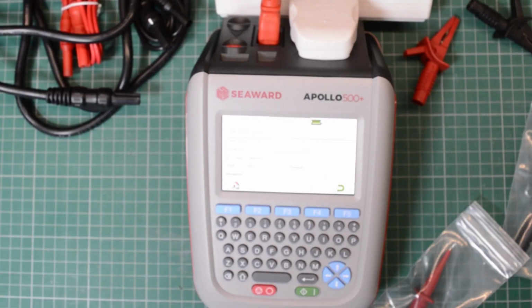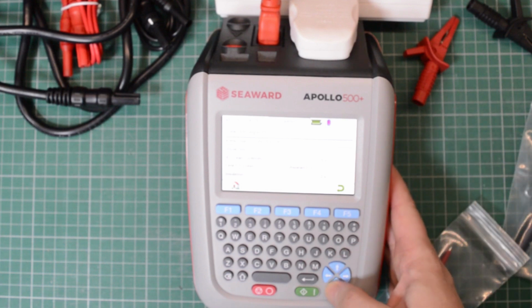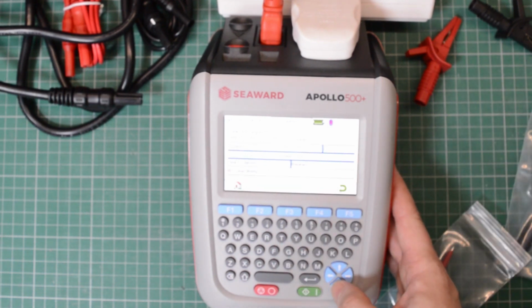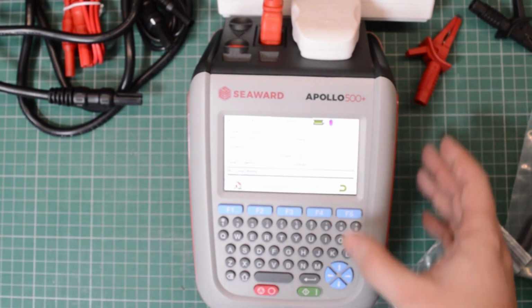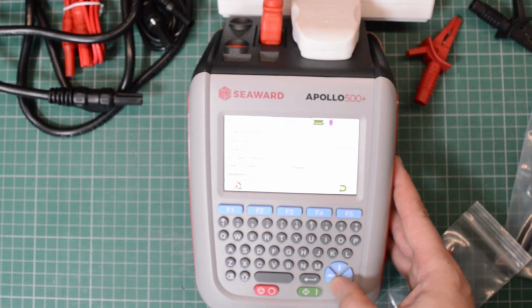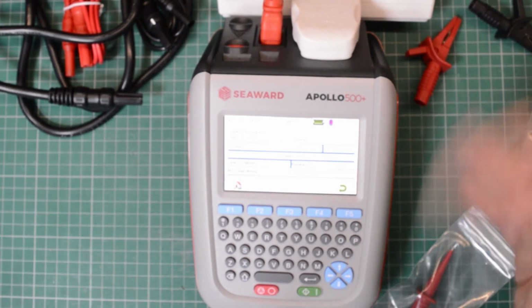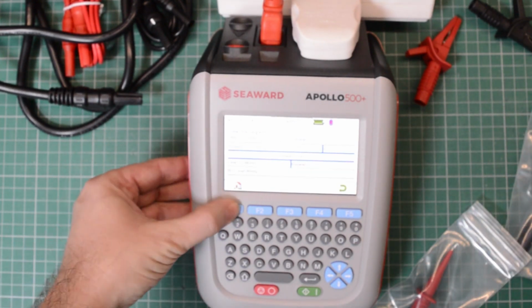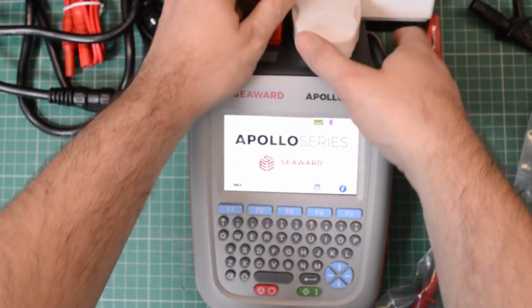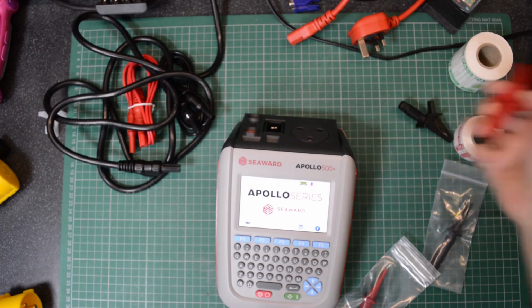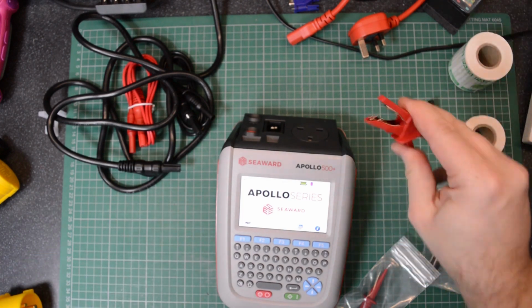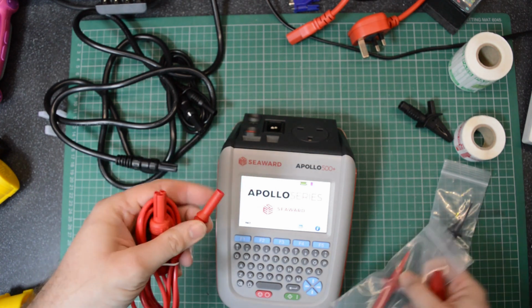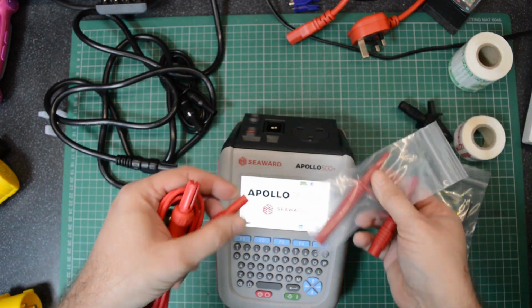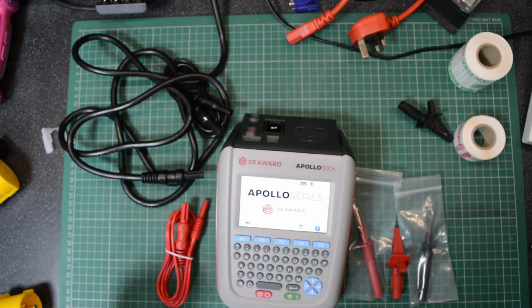You can view the test sequence. You can see it had 0.2 ohm continuity there. Limit is 1 megohm at 500 volts. Tested it as an IEC lead. Everything's okay. For class 1 devices, you need to do an insulation test. You've got probes and you've got the crocodile clips as well. Or if you want to do a handheld probe, you can. All this comes in the box.